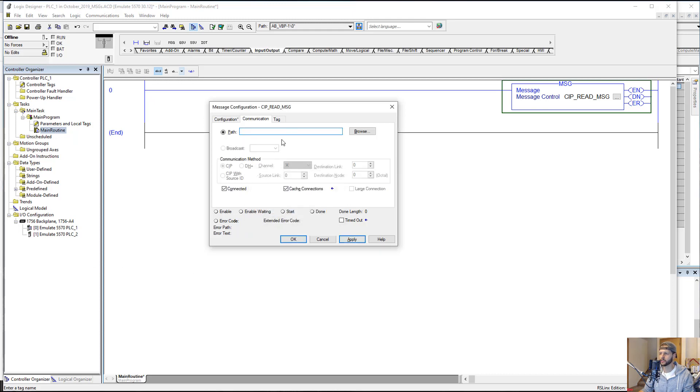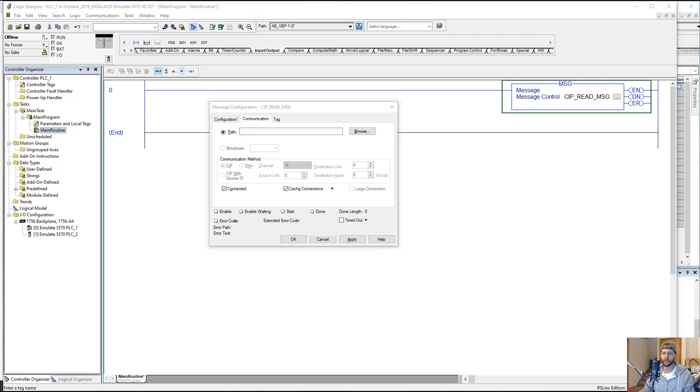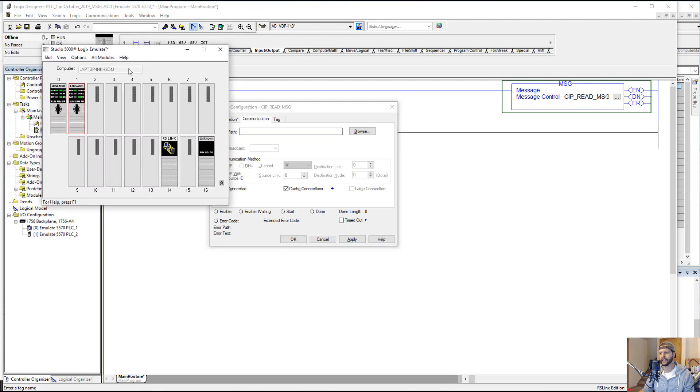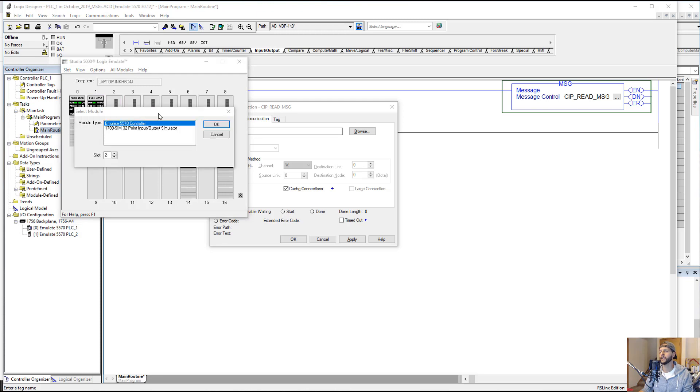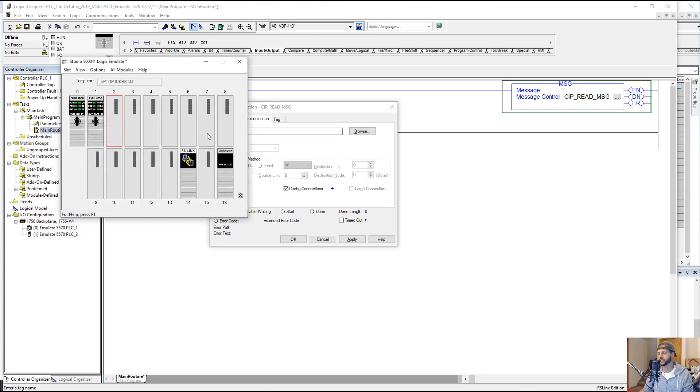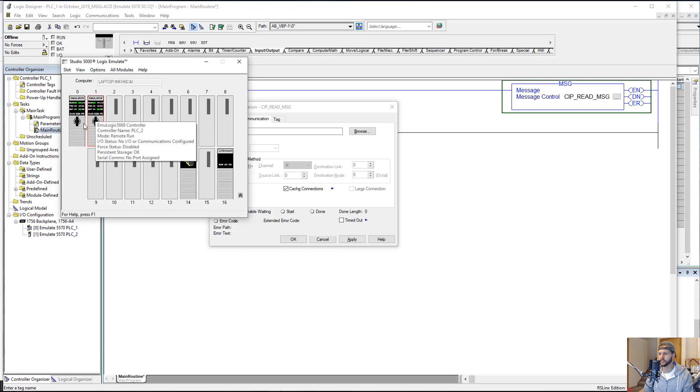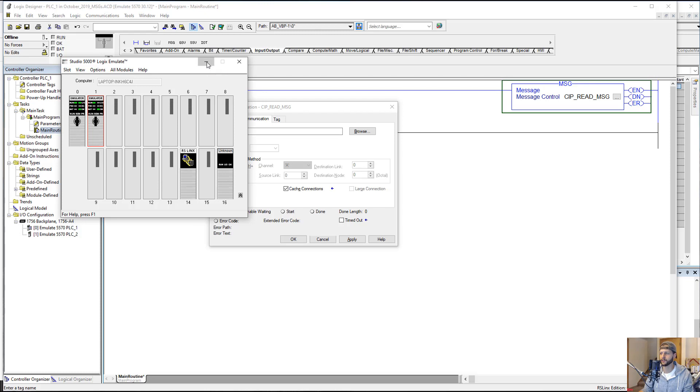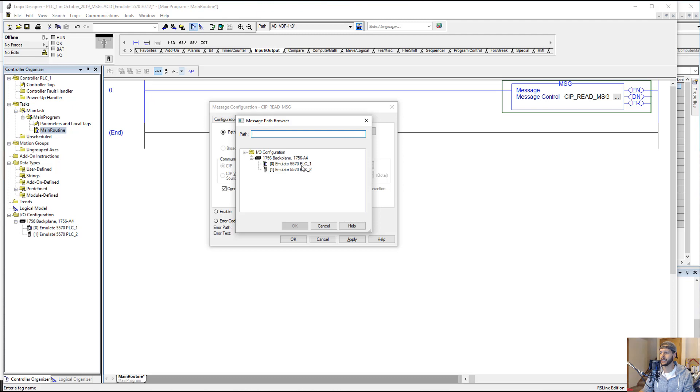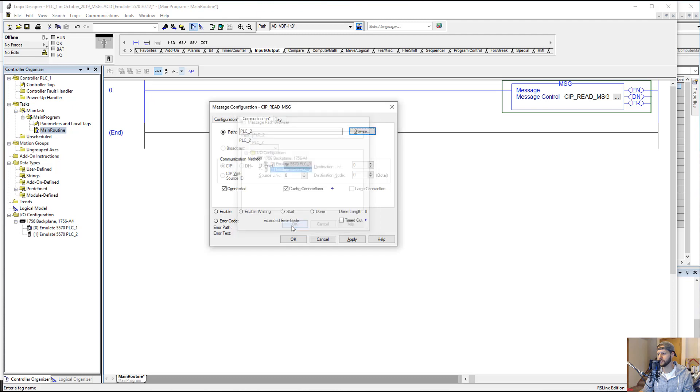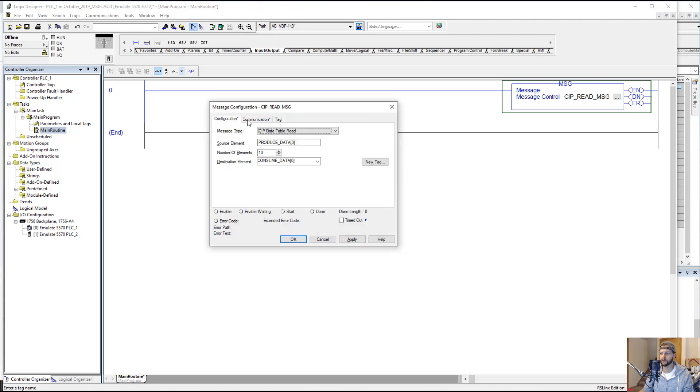We'll click OK and go to the Communication tab. You can see here in the I/O configuration, we have our main PLC, PLC1. It's in slot 0. And then we have PLC2 in slot 1, which I've added two controllers to our Logix Emulate software. You can see you can create controllers on the fly there. And that's what I've done. This is going to be our PLC1. This is our PLC2. I've actually downloaded this project to them before already. Since I set up PLC2 in our I/O configuration tree, we can click the Browse button and click in our I/O configuration tree, Browse Directly to PLC2. Click the Emulate 5570 there, PLC2.